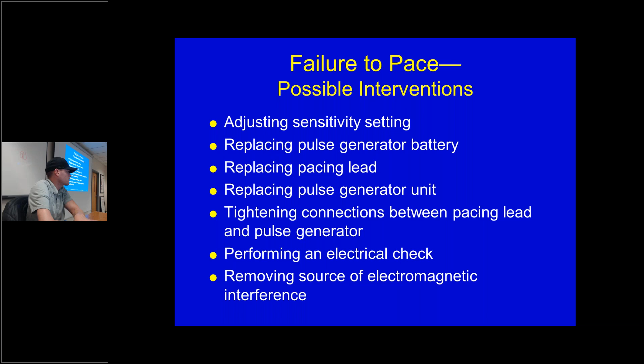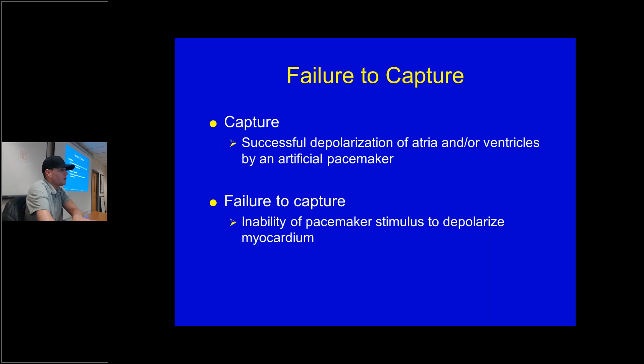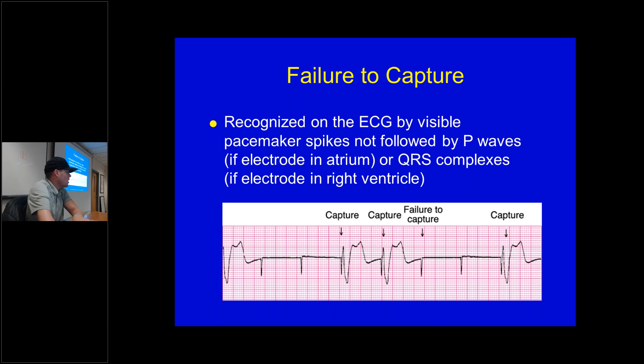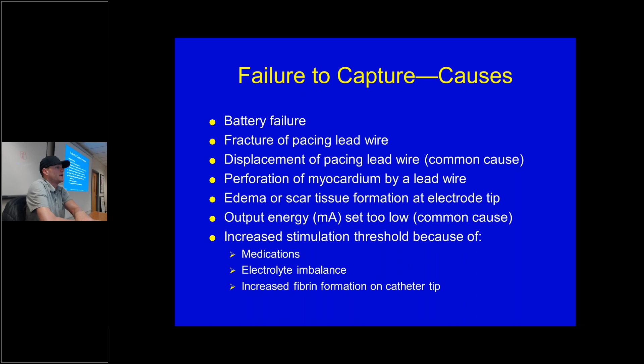All right, so capture, one of those key terms, successful depolarization. That's basically what it is. All right, failure is inability to have depolarization. So recognized on the EKG as you see the pacer spikes, but there's no complex, right? It's failure to capture. Sometimes when you're getting close to the right amps, it'll do this. You increase the amps a little bit, and you start getting capture. Failure to capture, all those same things. So in an internal pacemaker, you can not get capture if there's scar tissue built up at that tip. Like if it's dug a little bit too deep, the body responded a certain way, and there's a bunch of scar tissue, it might not be working as well.